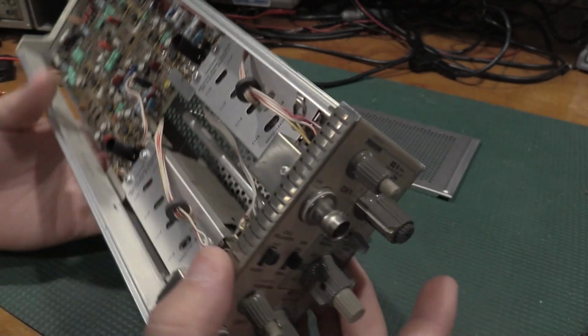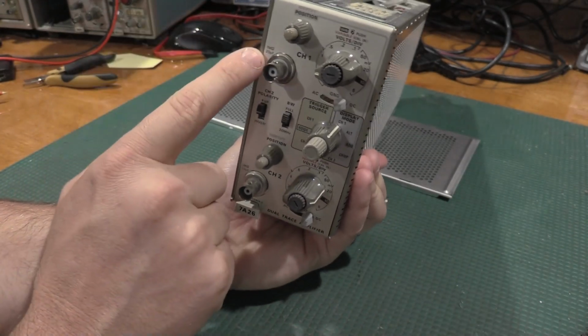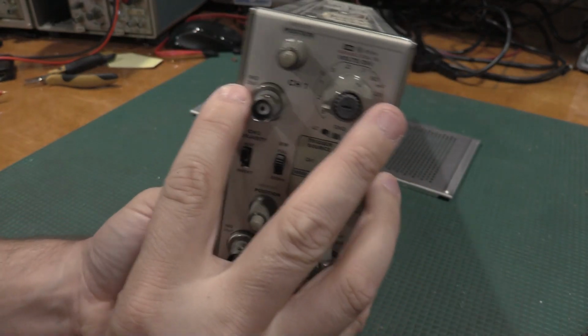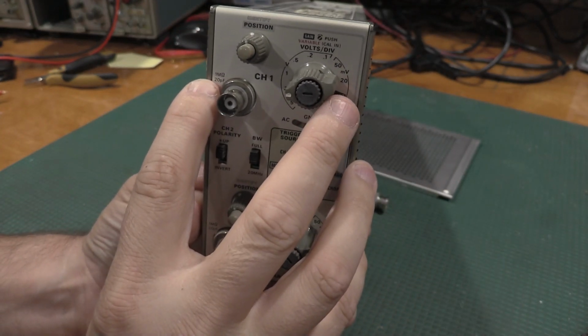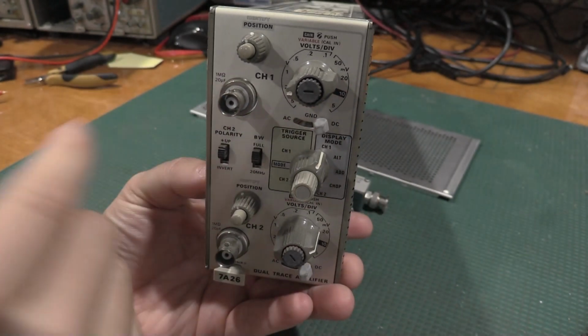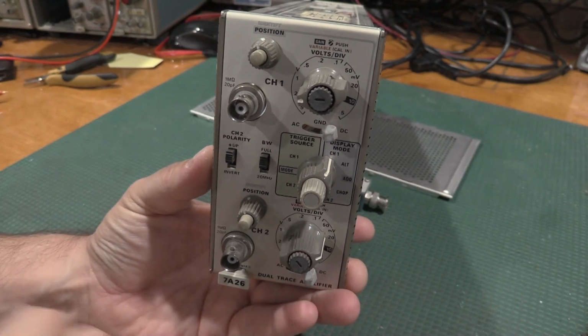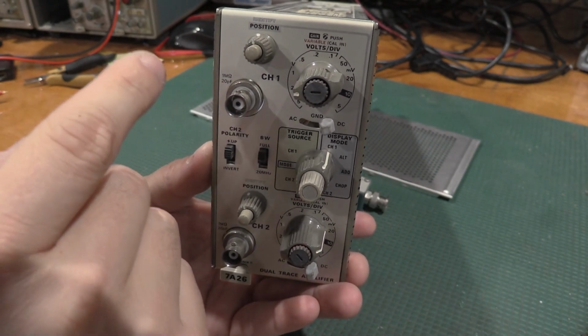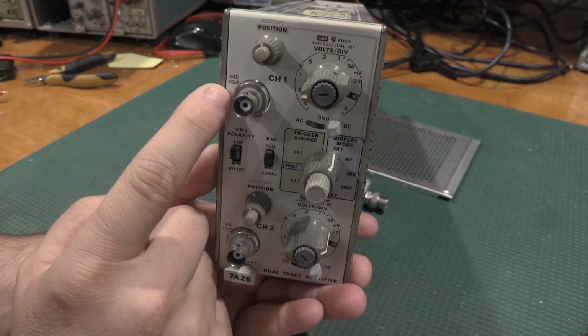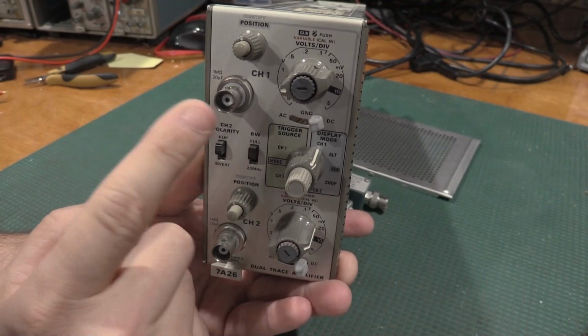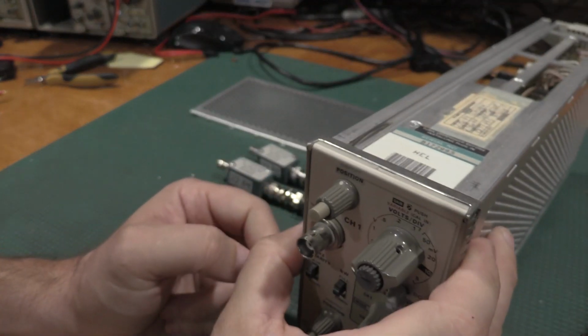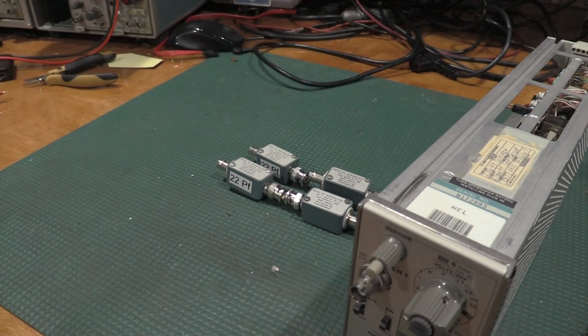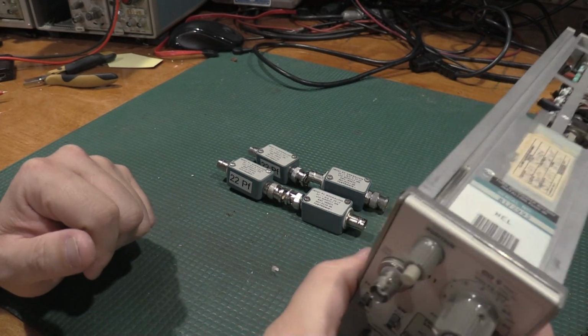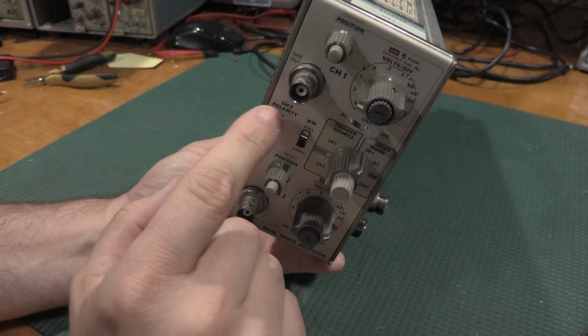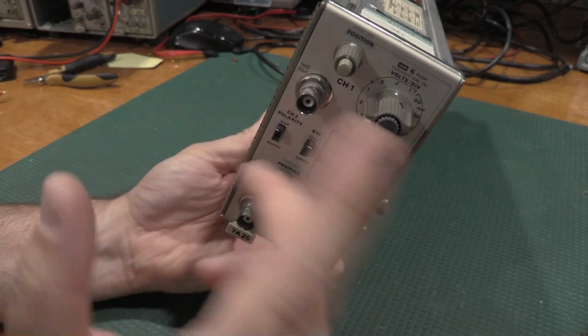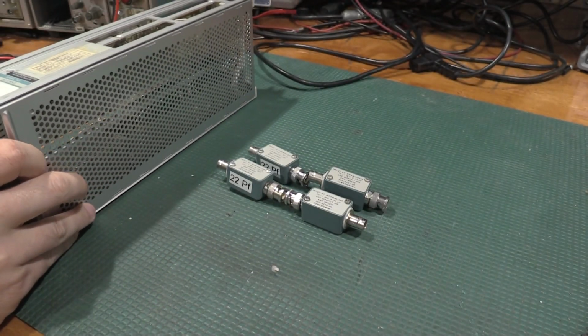So it's an order of operations that builds on itself as you go through the alignment and calibration process. On the front side of this scope we have an input with a nominal resistive impedance. Not really an attenuation; the attenuation's in the probe. We have a 1 megohm input impedance shunted by 20 picofarads of input capacitance. We want the input capacitance to be as low as we can get it within the ratings, due to capacitive reactance at higher frequency signals. As the bandwidth gets ratcheted up, this input capacitance becomes a much bigger deal. This is also true in the probes.